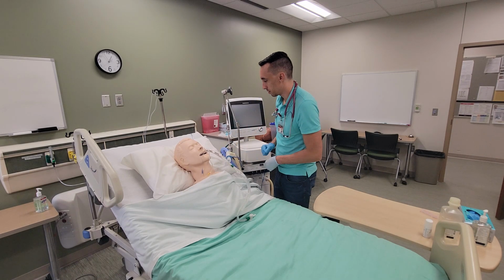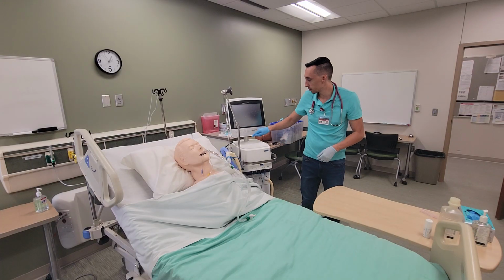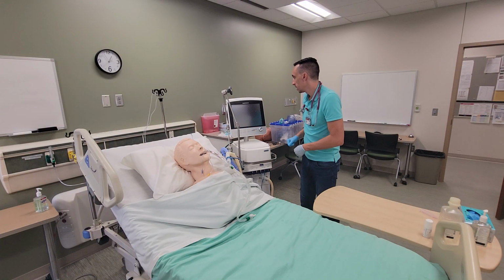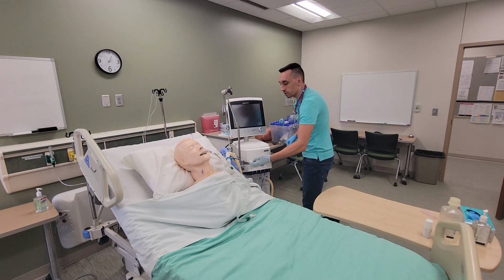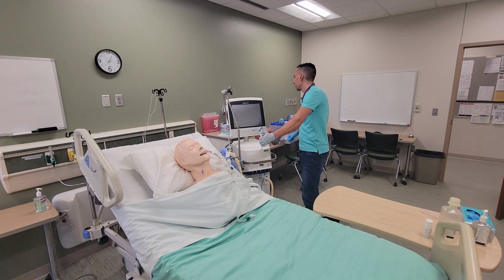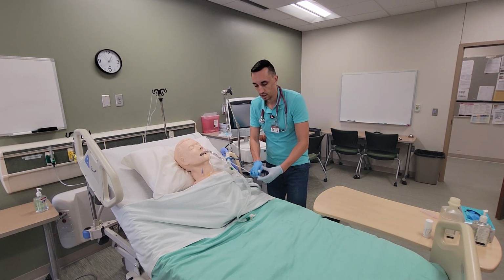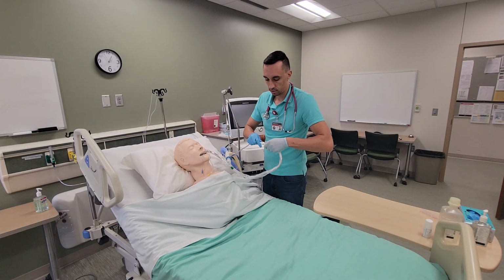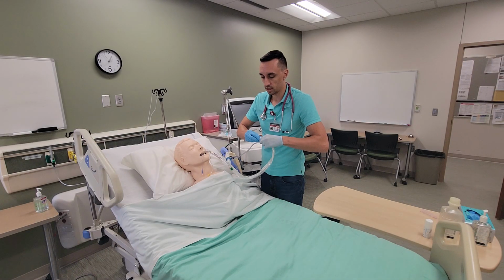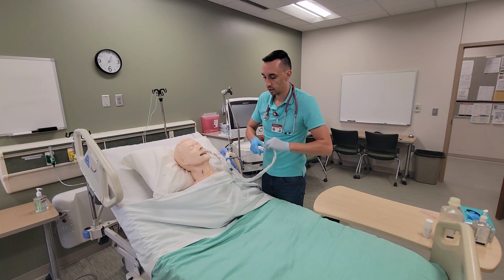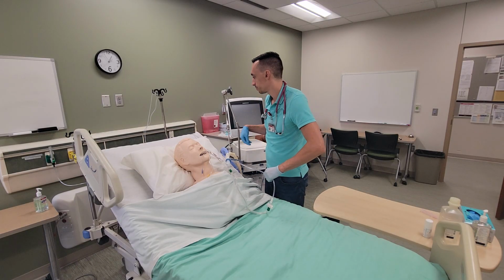Good. Now we're all connected. We're going to hyperoxygenate. Make sure my suction pressure is set at 150. It is. We'll connect our suction tubing. Make sure our button is unlocked. That looks good to go.